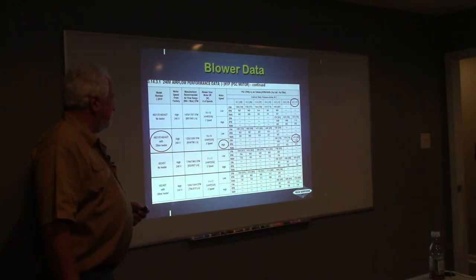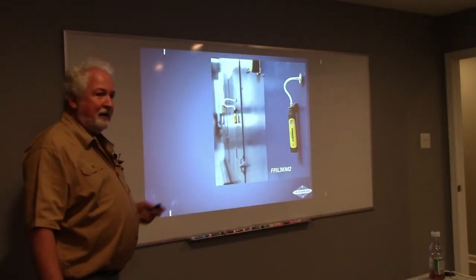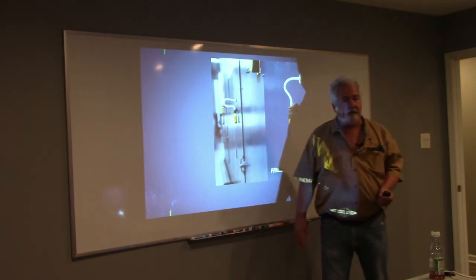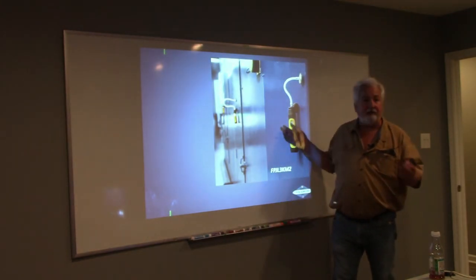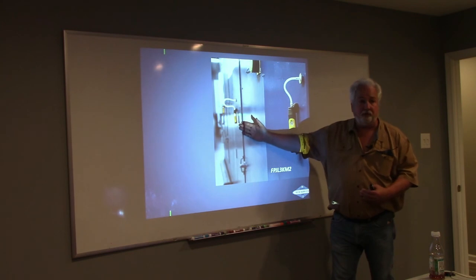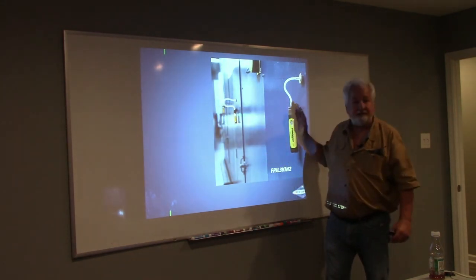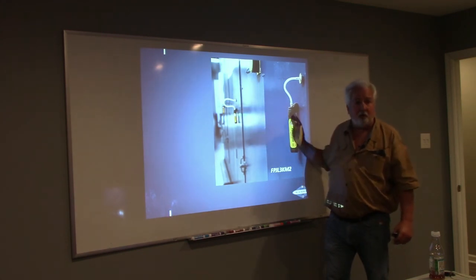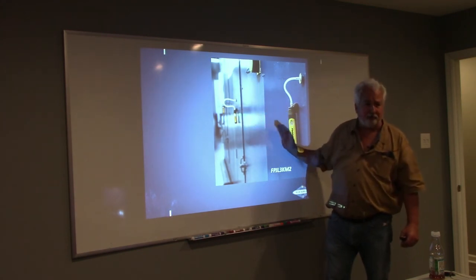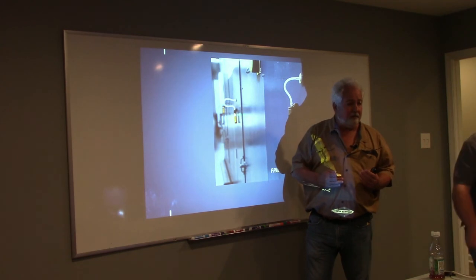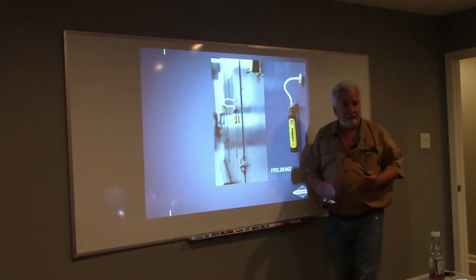All right. So, wait, what kind of manometer do you have? Digital Bluetooth. Works out well. These are great tools. I really feel very good about it. What I like about this is it's not just 2. You can add more. And as you add more, I can see the pressure drop across the coil, the filter, and the supply plenum. I can see all of those on my deal. Is everybody okay with that?